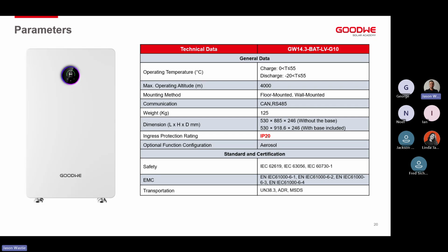So this is an IP20 rated battery. It can be installed on the floor using the feet that are provided. Otherwise, it can be wall mounted with the bracket provided. And we can install this obviously off the floor. It does have quite a hefty weight to it at 125 kgs. So do bear in mind that when doing the installation, use 2 or 3 people, please don't hurt your back.